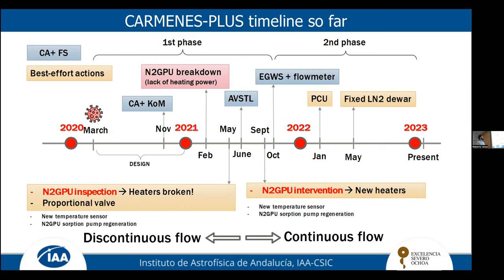The first one is February 2021, when we discovered that the preparation unit was broken and we didn't have the capability of evaporating the liquid nitrogen. It wasn't until May that an inspection discovered that the heaters, which allow us to evaporate the gas, were broken.